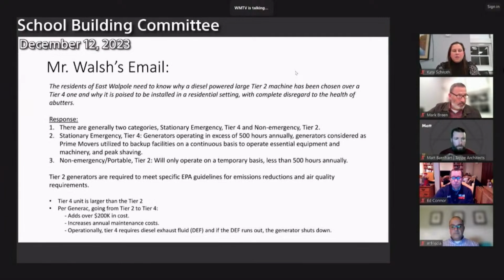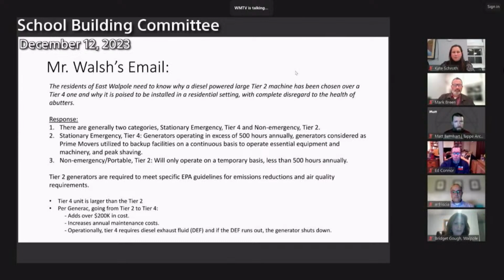And Kevin, do you want to just touch base on the tier 2, tier 4 question? Sure. This was a question regarding utilizing a tier 2 machine versus a tier 4. There's generally two categories for the generator: stationary emergency, which is the tier 4, and non-emergency tier 2. The stationary emergency tier 4 generators operate in excess of 500 hours annually. Again, that's a generator that's going to operate in excess of 500 hours a year.